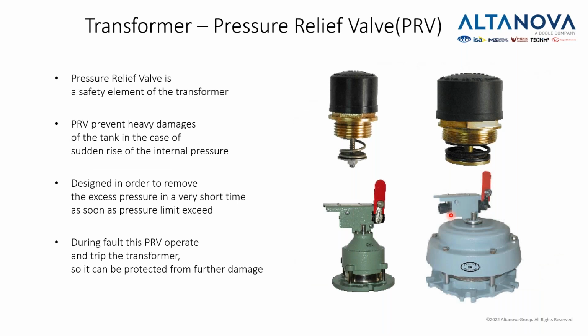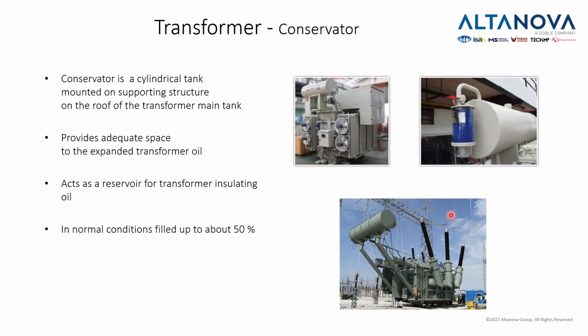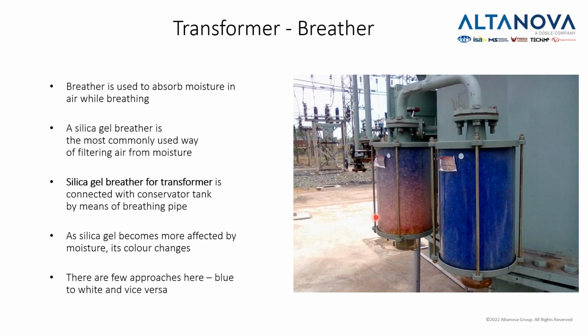If the pressure inside of the transformer gets too high, the valve will react and release the extra pressure into the atmosphere. We also have the conservator. It is this thing over here, you can see. When the pressure increases and the volume is bigger, some of the oil goes into the conservator. In the normal situation, this is up to about 50% full. And we also have a breather.